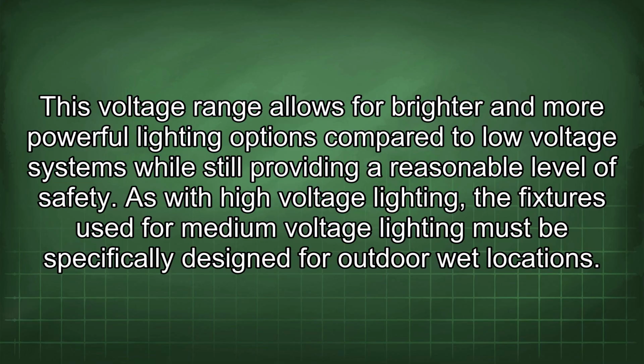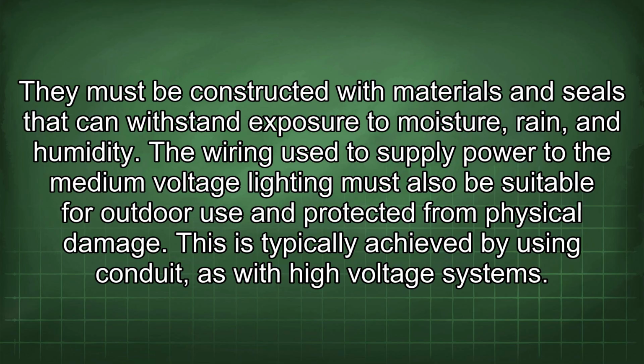reasonable level of safety. As with high voltage lighting, the fixtures used for medium voltage lighting must be specifically designed for outdoor wet locations. They must be constructed with materials and seals that can withstand exposure to moisture, rain, and humidity. The wiring used to supply power to the medium voltage lighting must also be suitable for outdoor use and protected from physical damage. This is typically achieved by using conduit, as with high voltage systems.